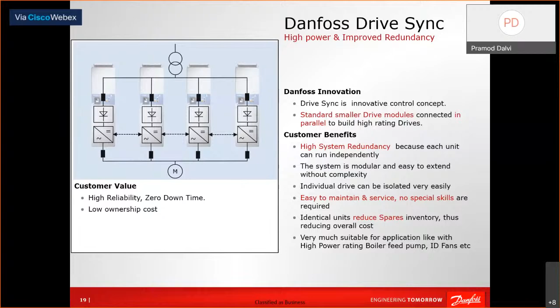This is a very important engineering feature for critical applications, for example an ID fan or a boiler feed pump, where we cannot afford downtime. There we can engineer it as a modular concept, where we size 3 drives for the required kW, and if the fourth module fails, the application will not stop. It will run on the reduced load. This is very popular in cement and metal industries, and it is picking up in the power industry or power plants as well. We have a number of installations in cement and metal industries, and we have started this in the power industry.